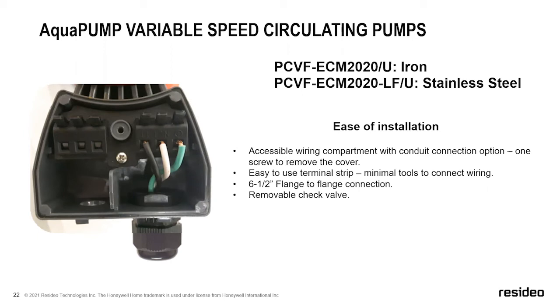They are push button tabs. So we recommend using solid wire. The image here is showing stranded. I did that because you could show that stranded wire does go in here just fine. So if you're using pigtails or whatever you're using, there is some room to do your wiring. It's not overly crowded inside of there.